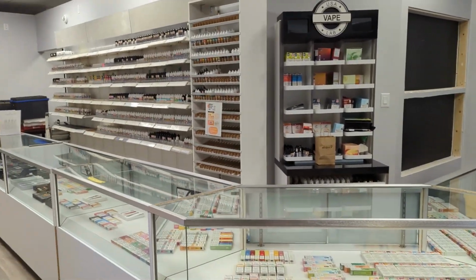And then the third condensate issue we had this week was at a vape shop. They complained there was water leaking out of the ceiling. So we took a look at it, and they have a condensate pump there that was full when we got there. And so we're like, okay, the pump is faulty. But if you just tap the pump on the side, it energizes and pumps out, no problem. An intermittently faulty condensate pump is not a risk we're willing to take, because we tested it a second time, and once again it wouldn't pump out until we gave it a little tap on the side. So there must be some debris, or something's faulty with the little micro switch inside there. Inside there's a float, and as the float lifts up, it triggers the little switch, I guess. And so I guess that's just not triggering.